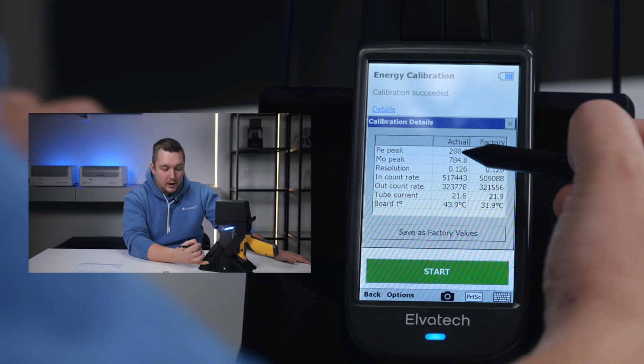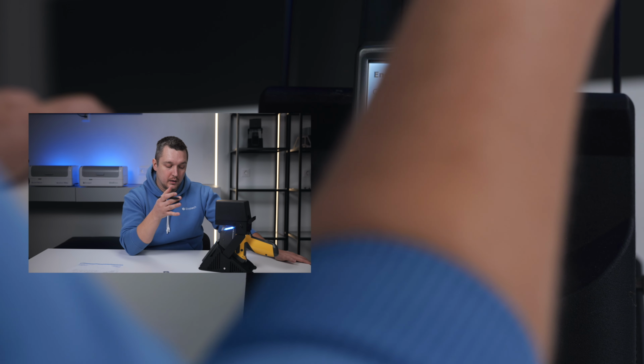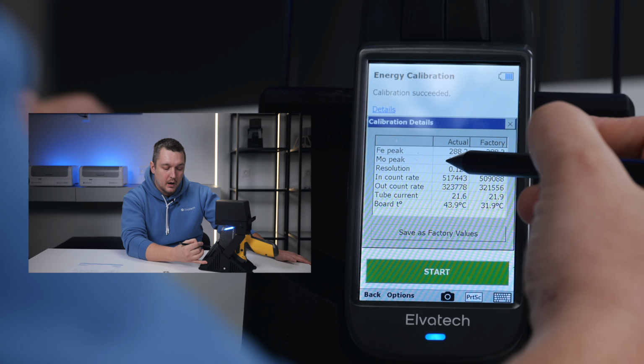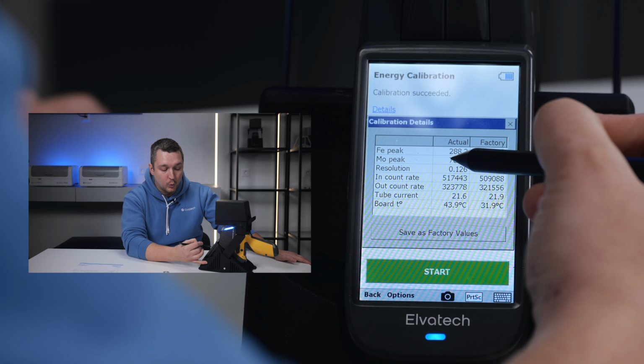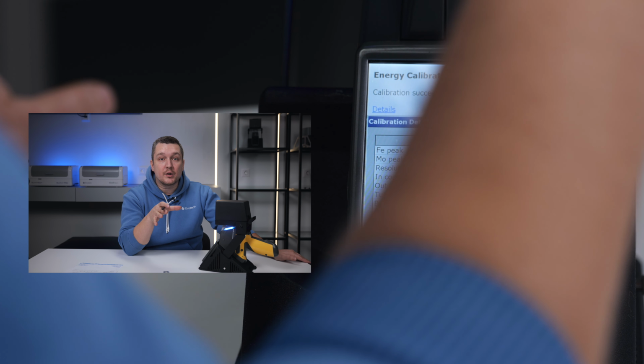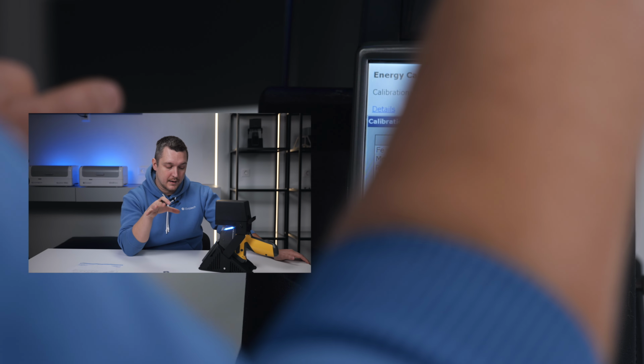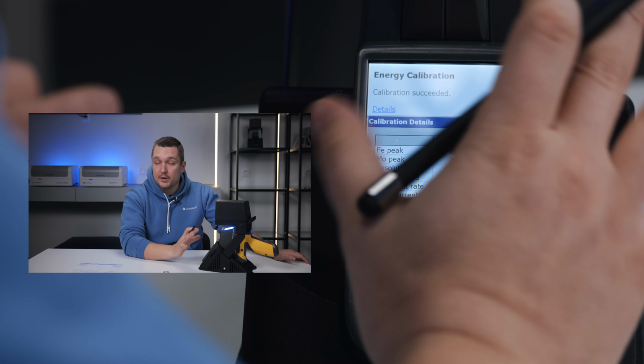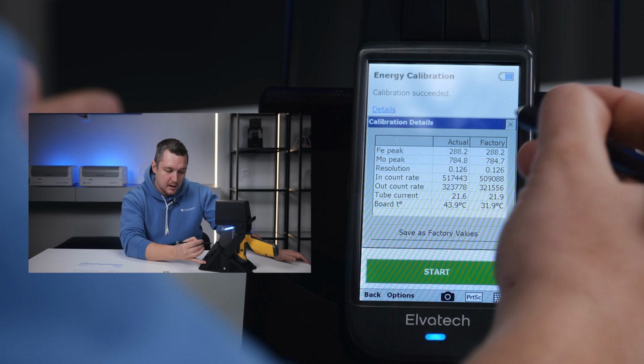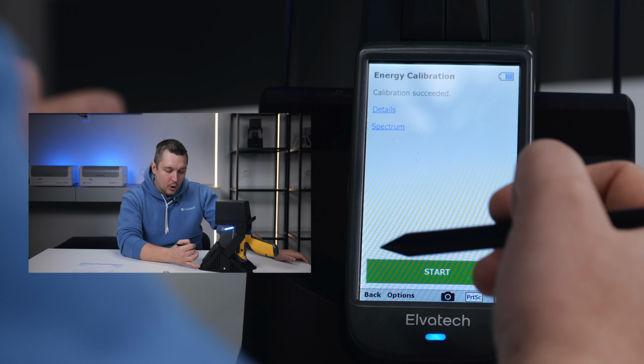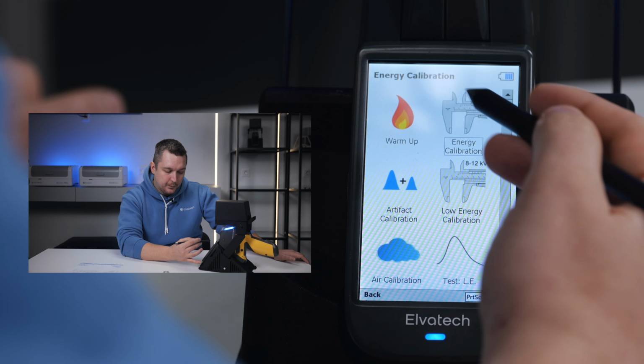If you perform the energy calibration for the heavy elements and you see here, for example, 0.141, it means that something is wrong with the analyzer, and you should contact our service department, so they will provide the remote diagnostic of your analyzer. But here we see that everything is okay. So we just close this table and we go back. And now we need to perform the low energy calibration.